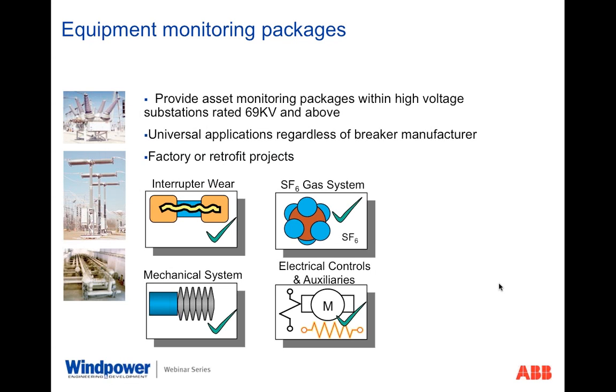SF6 gas algorithm: as we all know, the EPA, or U.S. Environmental Protection Agency, has regulated that every customer in the U.S. is required to report the amount of SF6 gas usage on an annual basis. As of today, there are no apparent thresholds for the amount of usage except for California. CARB, the California Air Resources Board, part of the California Environmental Protection Agency, requires a threshold percentage that will be reduced 1% on an annual basis, as well as potential penalties for non-compliance. So our advantage of this algorithm is not only to provide early detection and rate of leak prior to the traditional contact alarms. This will allow adequate time to schedule an outage to not only repair the leak, but reduce the amount of SF6 gas losses.